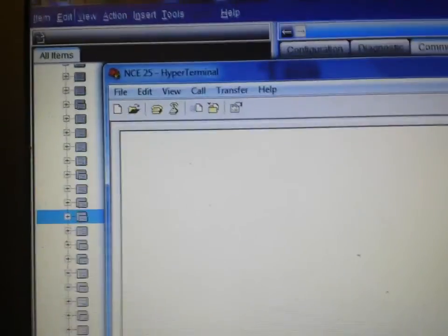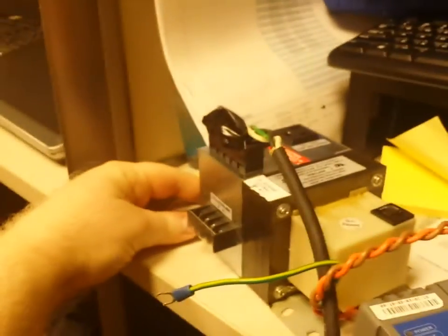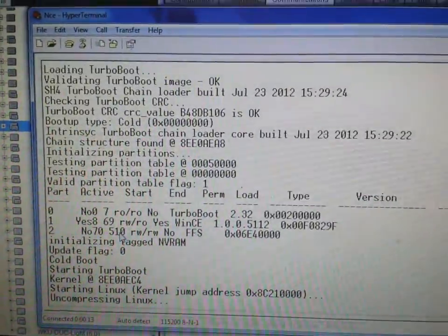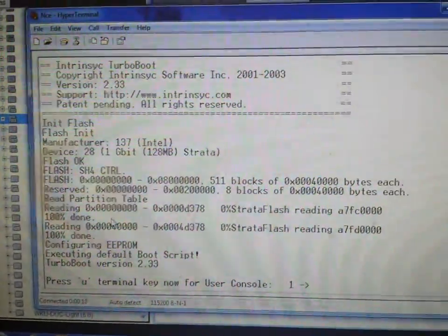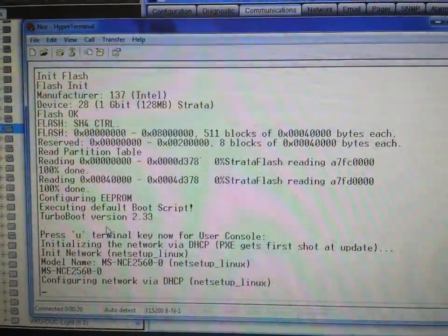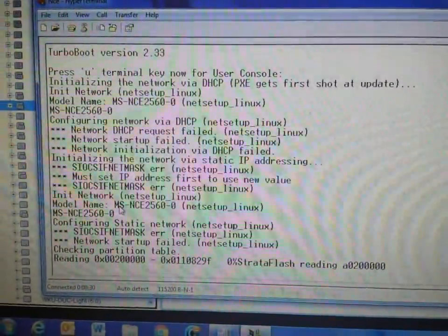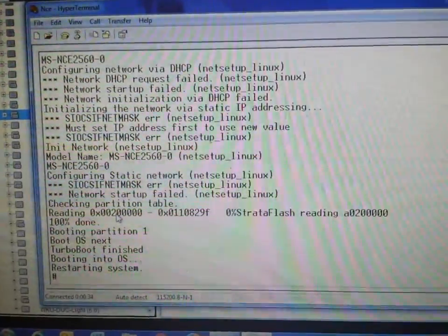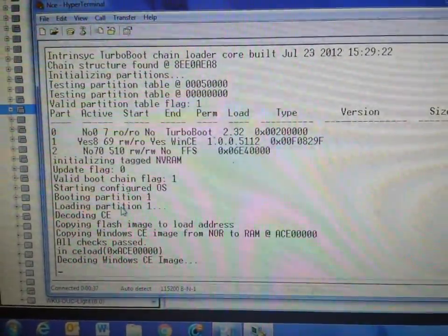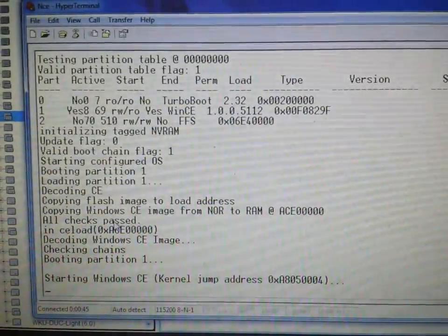So now that we have that completed, we are ready to put power on our device. If you have configured everything correctly, once you restore the power to the NCE, if you watch your HyperTerminal screen, as you see here, it will actually spit out a lot of the internal settings of the device. There's quite a bit of information that it will scroll through, but eventually it will open a section where it tells you the name of the device as well as its IP address. It also gives you a little bit of information about some of the network settings within that device as well. So we will let this run for just a few moments, and eventually we should see the name and IP address.